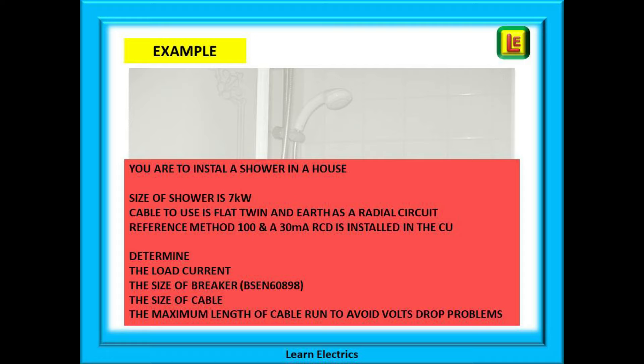Why worry about the length? If it is less than the maximum permitted length, then we know that we will not have a voltage drop problem in the cable at full load. There will be sufficient voltage at the point of use to run the shower properly and safely.